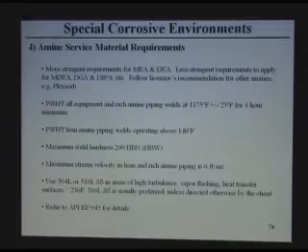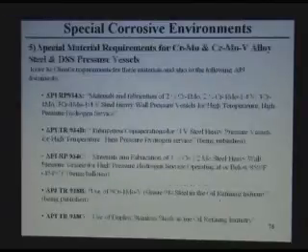Maximum hardness again 200. You have to control your velocity in piping below a maximum of 6 feet per second. In areas of turbulence, vapor flashing, and heat transfer surfaces, we have to use stainless steels, and I prefer to use 316 because of the moly. It is more resistant, and there is an API document that gives more details on this subject.